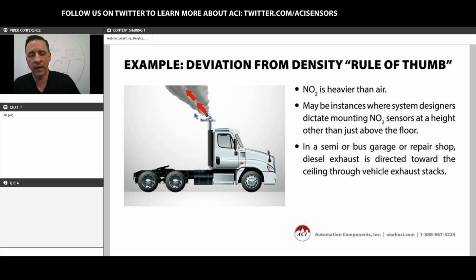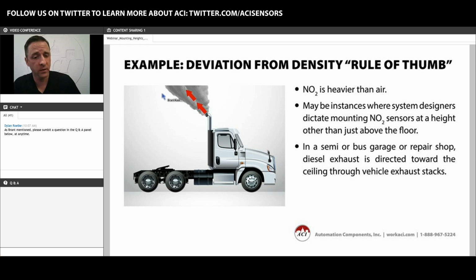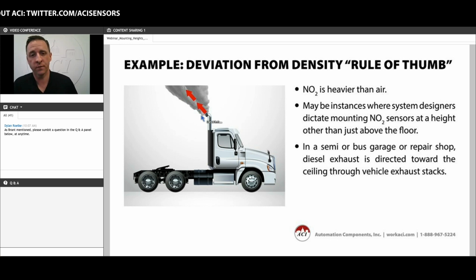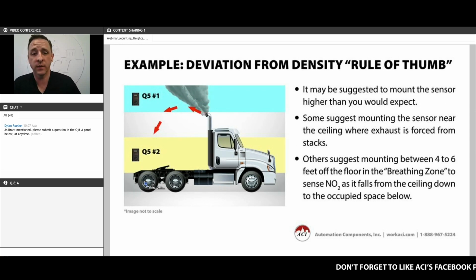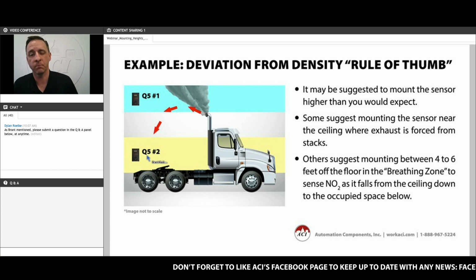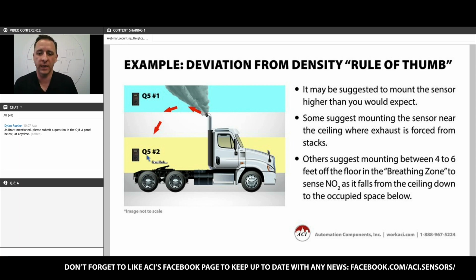In these applications, we would recommend mounting an NO2 sensor high towards the ceiling, because the gas is first going to be exhausted high out of this stack, and because it's hot, it will rise to the ceiling. A sensor mounted up high will give you the first chance, or the best chance, of detecting that gas immediately upon its exhaust into the space, and allow you to turn that fan on and exhaust that gas from the space before it would get to the breathing level. In these cases, we would also recommend mounting a second sensor in the breathing zone. Any gas that is missed by the first sensor, or cools and sinks quickly, would be detected as it enters the breathing zone, to give you another added layer of protection. So this is one example where we would deviate from the specific chemical density mounting height recommendation.